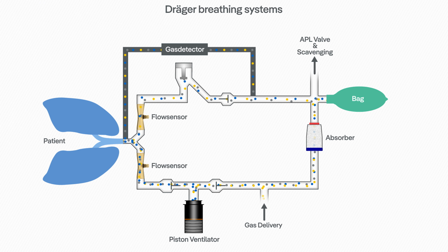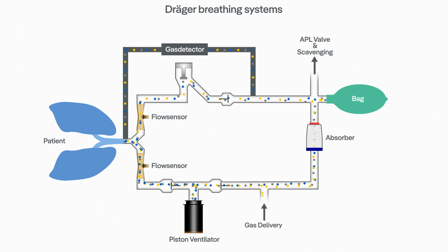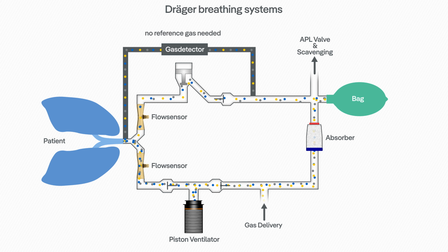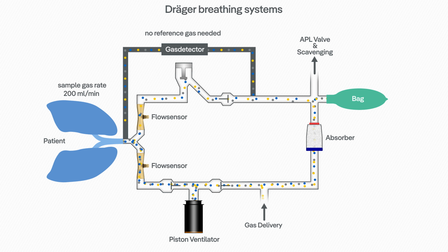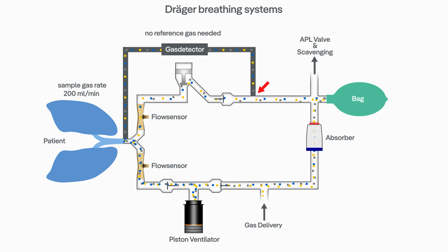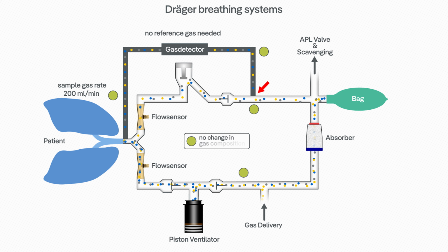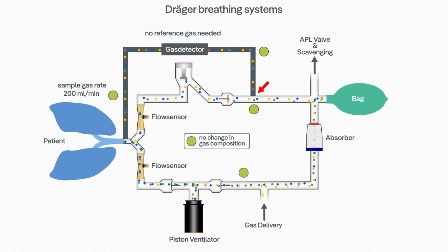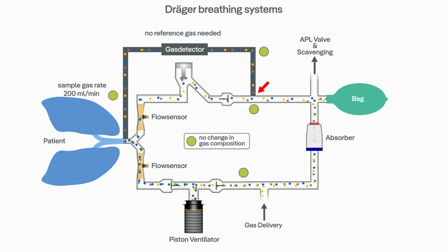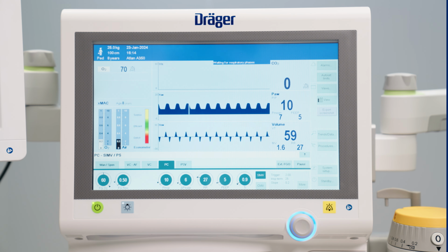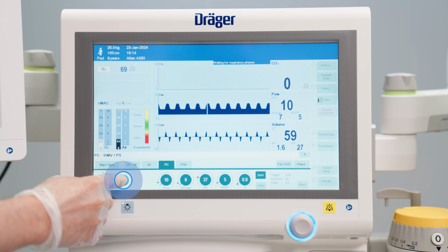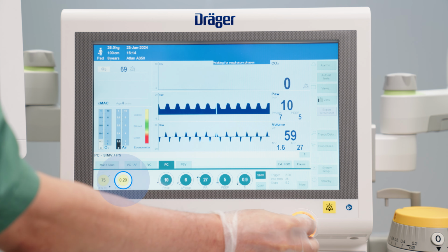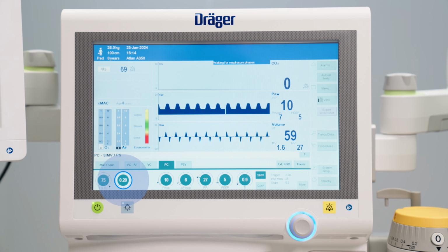Dräger deploys paramagnetic as well as electrochemical O2 sensor technologies, which do not use reference gas, so the sample gas, which is always returned back to the breathing system, does not change the gas composition, and there is no systematic leak which needs to be compensated. Therefore, with Dräger anesthesia devices, it is possible to operate efficiently at flow rates of less than 500 milliliters per minute.